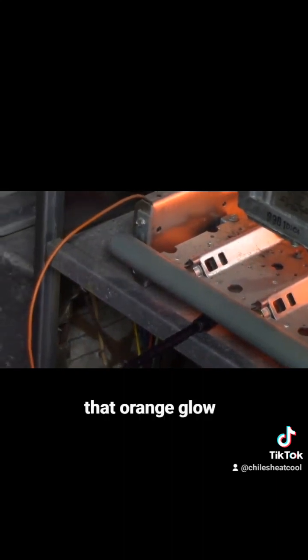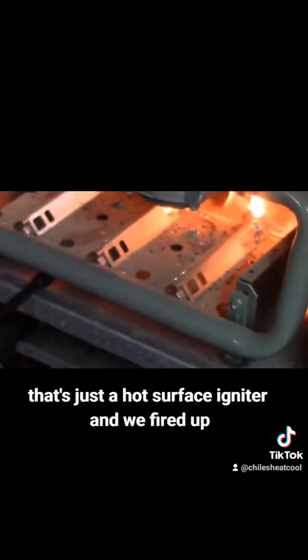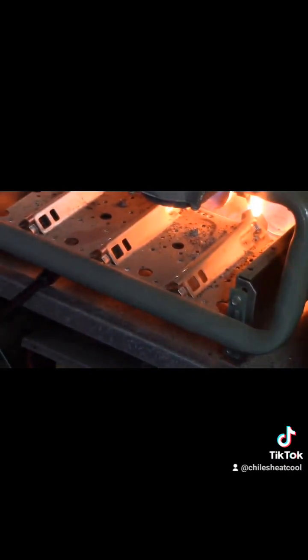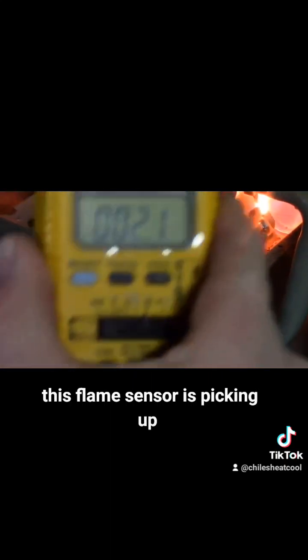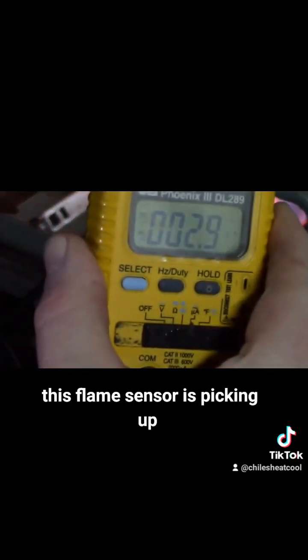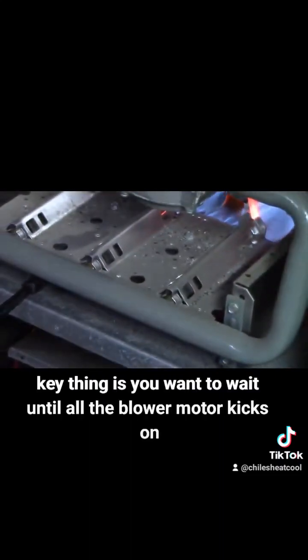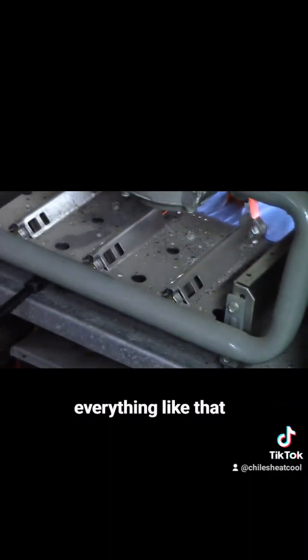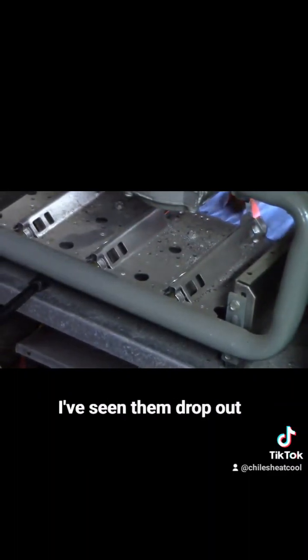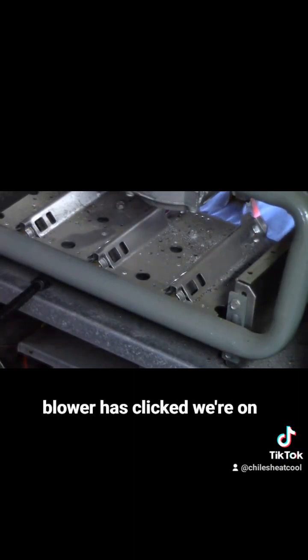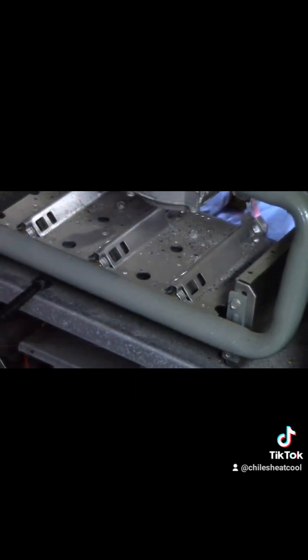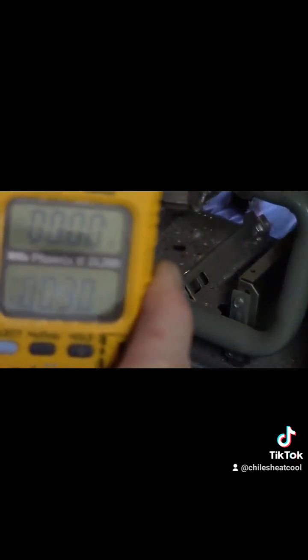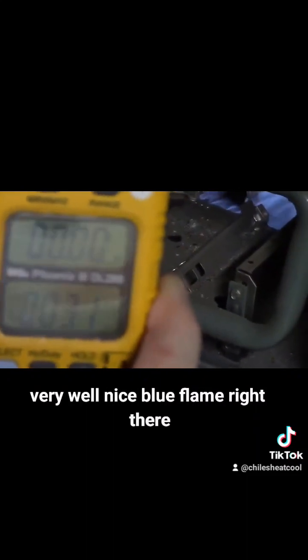That orange glow, that's just a hot surface igniter. And we fired up. This flame sensor is picking up pretty good reading, really good reading. Key thing is you want to wait until all the blower motor kicks on, all the electronics, everything like that. I've seen them drop out. Blower has clicked, we're on. 3 microamps DC. Very well. Nice blue flame right there.